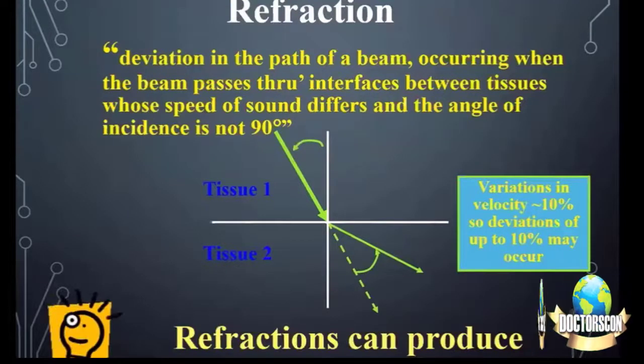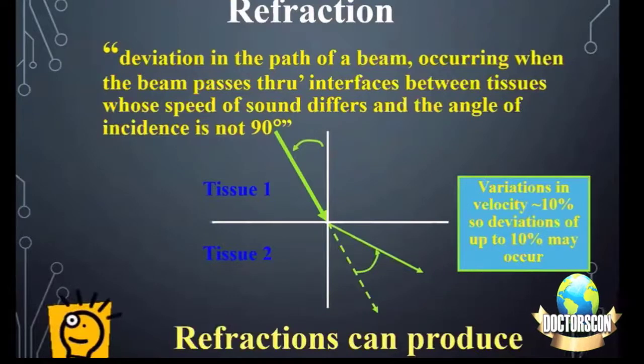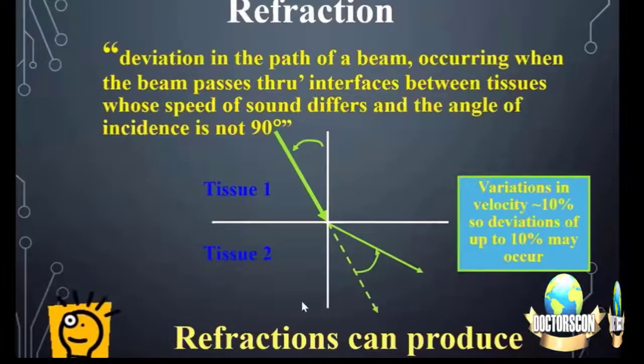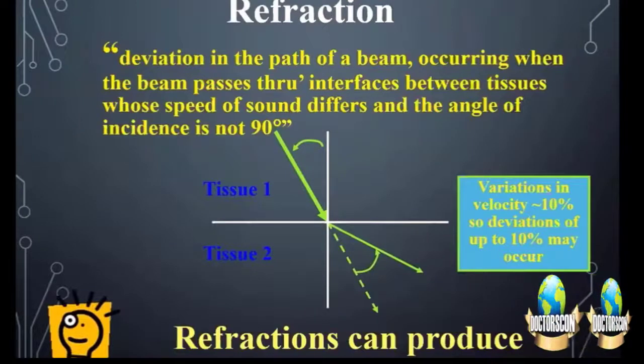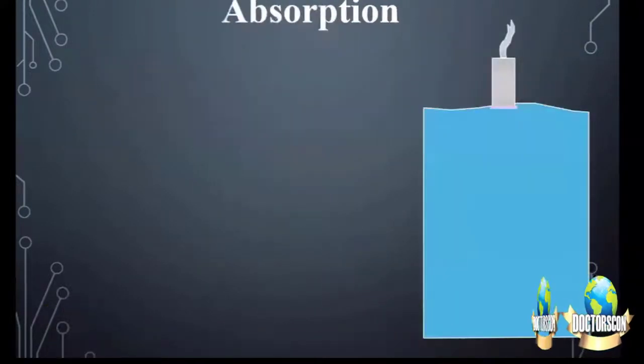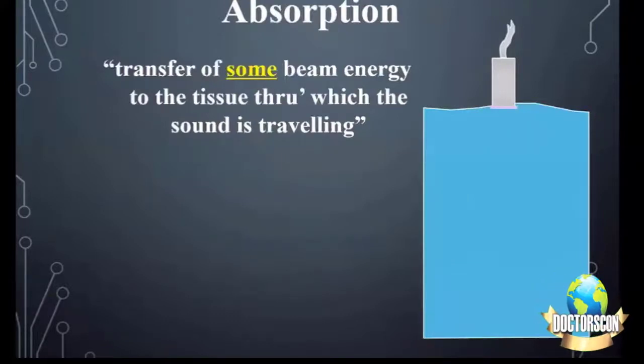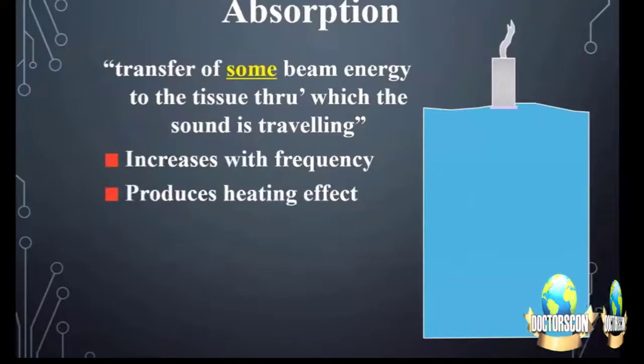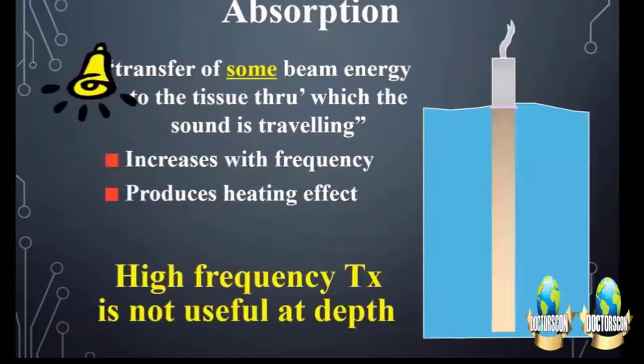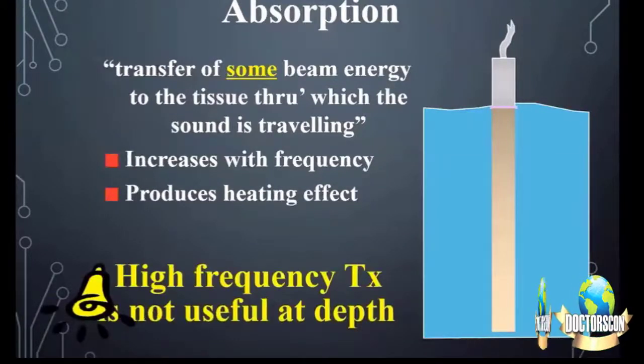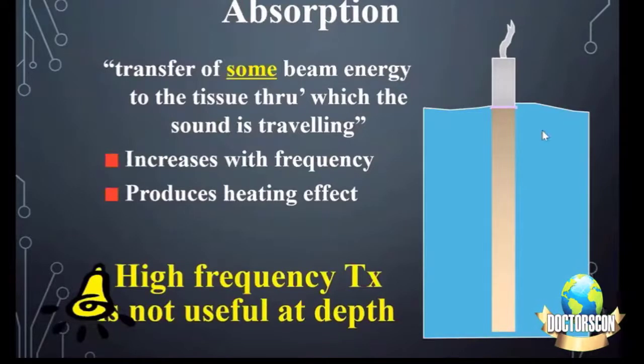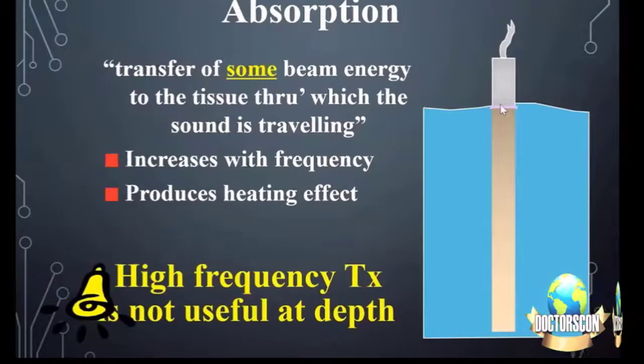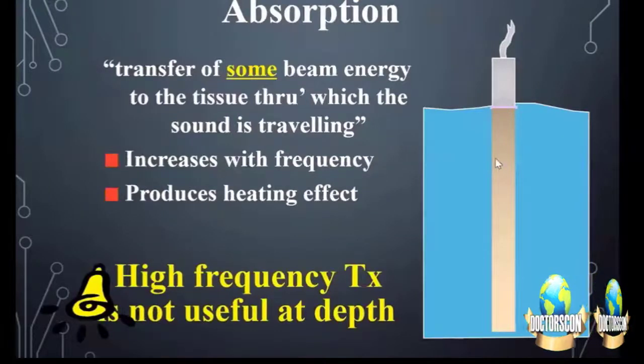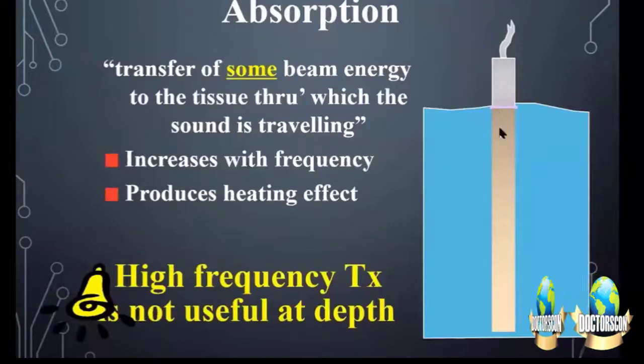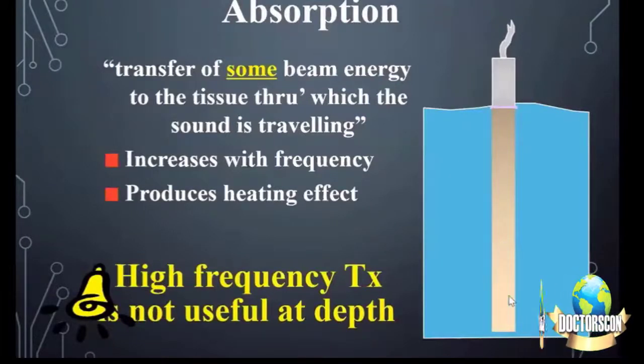So variation in velocity is about 10%. So deviation of up to 10% may occur. Refraction can produce misregistration. Then is absorption, the transfer of some beam energy to the tissue through which the sound is traveling. It increases with frequency and produces a heat effect, and a high frequency transducer is not useful at depth. So the high frequency transducers are used to see the structures which are superficial, and low frequency transducers will show us the structures which are deeper.